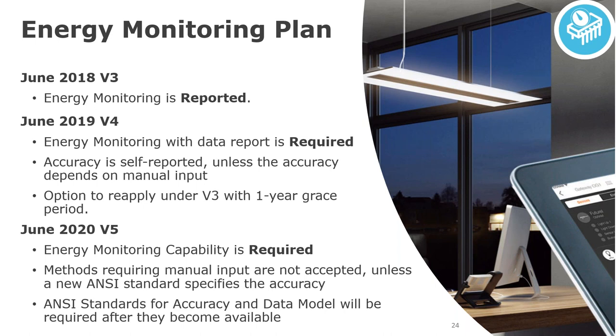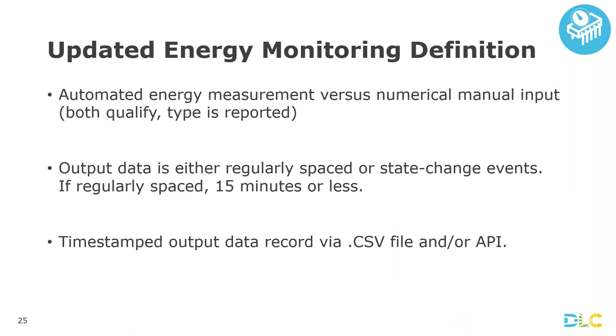Here are the main points in the updated energy monitoring definition. First, there is a distinction between automated energy measurement versus numerical manual input. This year both types will qualify, but next year the numerical manual input method would drop off unless there's a new standard to define its accuracy. This addresses the concern that efficiency programs have noted: when manual input is required to make energy monitoring work, it often doesn't get done. Automated systems will definitely continue to be qualified next year and going forward. The second part is that output data is either regularly spaced or state-change events, and if regularly spaced the spacing is 15 minutes or less.